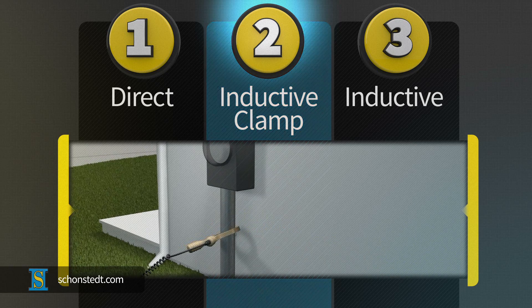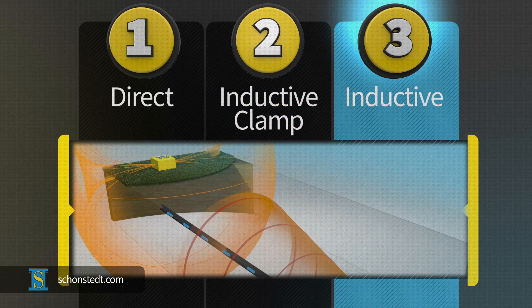The inductive mode is often referred to as the drop the box method because the transmitter's box is placed on the ground near the pipe or cable to induce the current. It produces far less current than direct or inductive clamp and should only be used when the other modes are not practical.